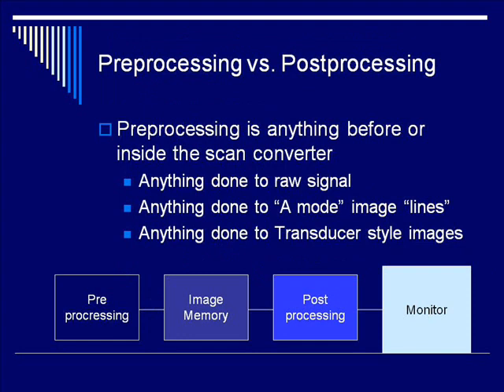Now, on to pre-processing and post-processing. Remember that we've just discussed one part of the role of the scan converter — we still need to discuss some things that happen in or around it. The image we have is composed of rows and columns of pixels, but we still haven't filled in the gaps or shaped the image correctly. All of the signal processing that converts from what the transducer sees to what we see is either pre-processing or post-processing. Pre-processing is signal processing that happens before or inside the scan converter — anything done to a raw signal, to A-mode image lines, or to transducer-type images.